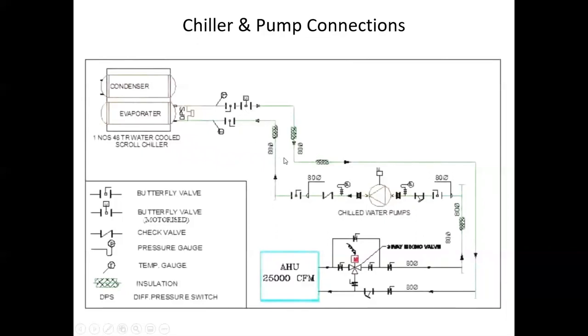I don't care. And then around the pump, I got a couple details on pumps here. This one certainly says chill water on it. Coming into the pump, we've got a butterfly valve. We've got a strainer. This is, I think, a sensor. This would be a union, that sort of thing. On the suction side, you've got these two, and you may want to put a suction diffuser on this. I'll talk a little bit more about that in a second when we get to the next diagram.